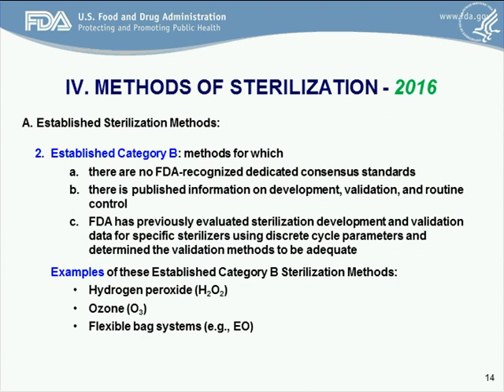Taking a look at established category B — these are methods for which there are no FDA recognized dedicated consensus standards. There is published information on development, validation, and routine control, and FDA has previously evaluated sterilization development and validation data for specific sterilizers using discrete cycle parameters and determined the validation methods to be adequate. Examples of established category B are hydrogen peroxide, ozone, and flexible bag systems.